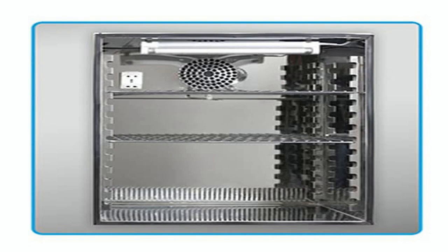It's the solid metal chassis and the compressor that's built to maintain a sub-zero floor temperature. In practice, that means once you set the temperature, the unit can hold the set point without the kind of hunting you sometimes see on cheaper models. For a lab that runs time-sensitive cell cultures, that stability can translate into fewer lost samples.